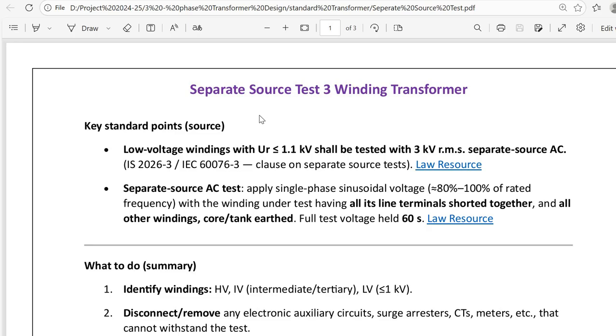I am going to teach you about separate source of three-phase transformer testing. This test is mentioned in IEC 60076 part 3. Low voltage winding, if less than 1.1 kV, shall be tested at 3 kV RMS.